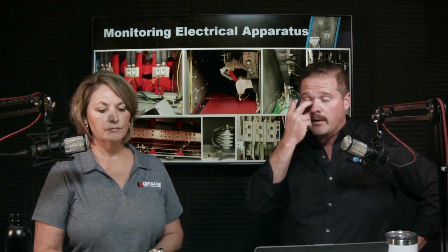This unit is data logging locally, but provides the connectivity out via Ethernet IP, Modbus RTU, or Modbus TCP IP. By adding our gateway, either one of our cloud gates, either via LTE or Wi-Fi, we're able to bring that data that's just local, or even potentially inaccessible in remote locations, up to the cloud. I think we've even had conversations recently with clients looking to put Starlink on their units, and as long as Starlink's talking Wi-Fi, we can provide a Wi-Fi connection to the cloud via even a Starlink offering for really remote locations.